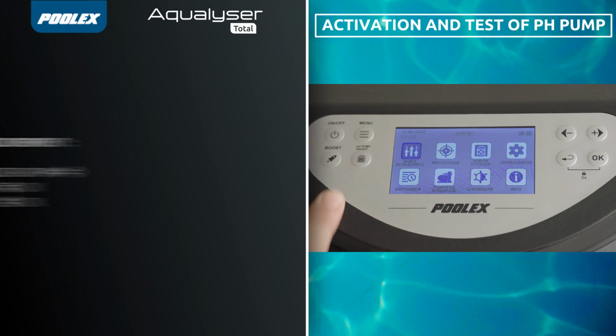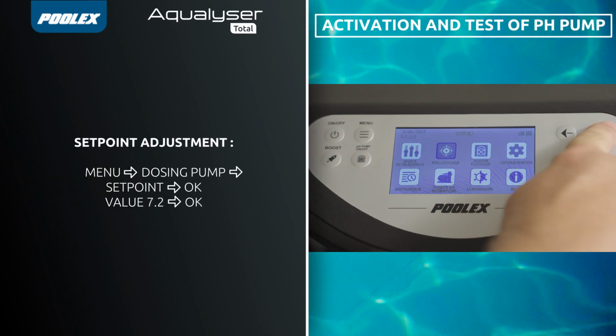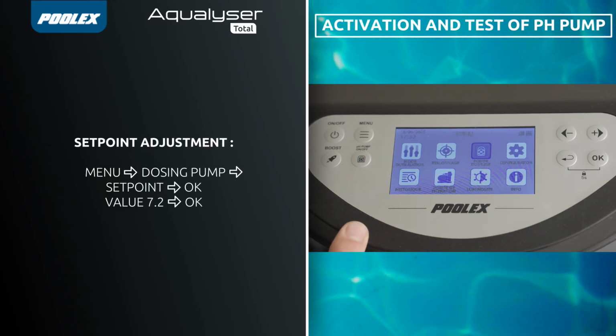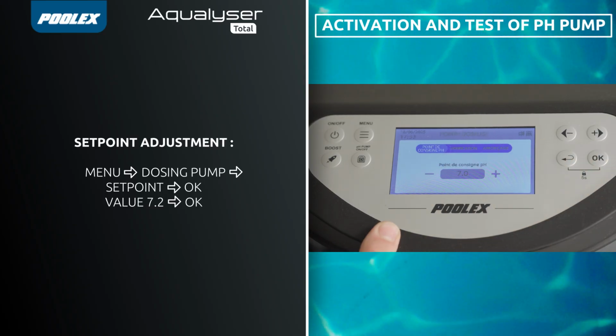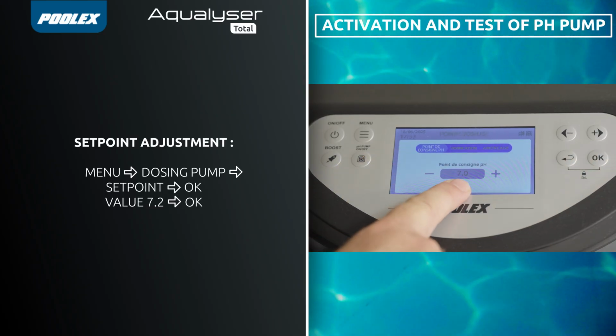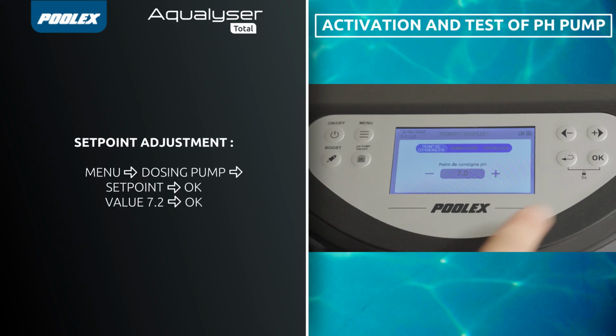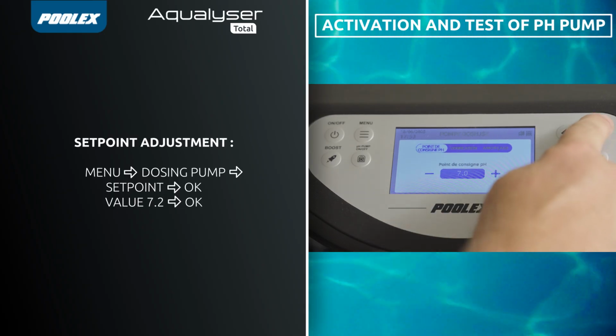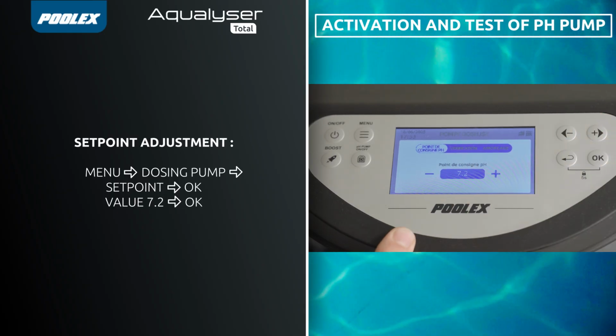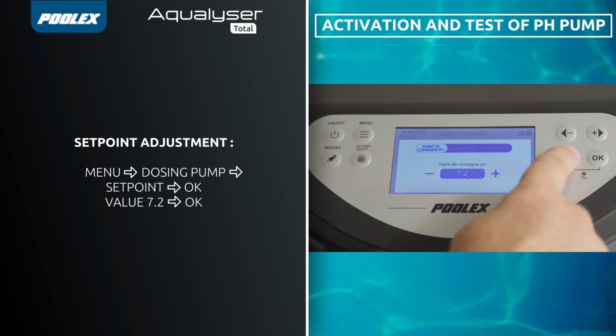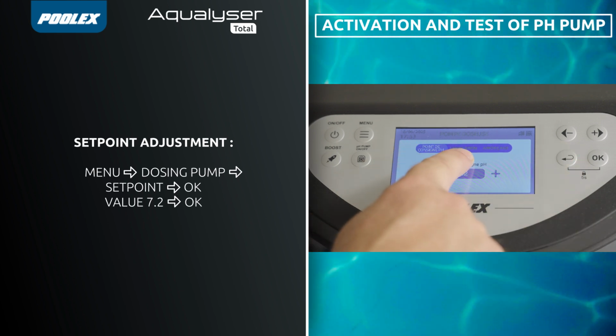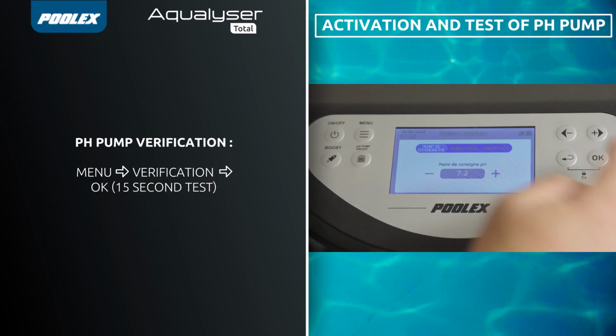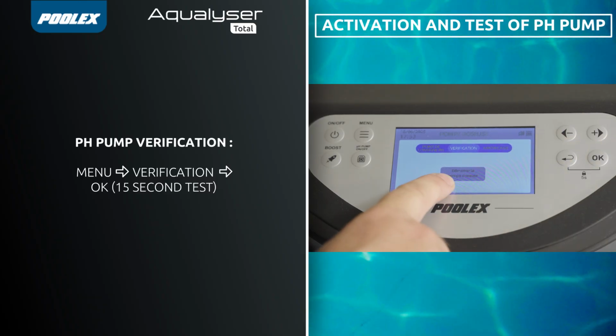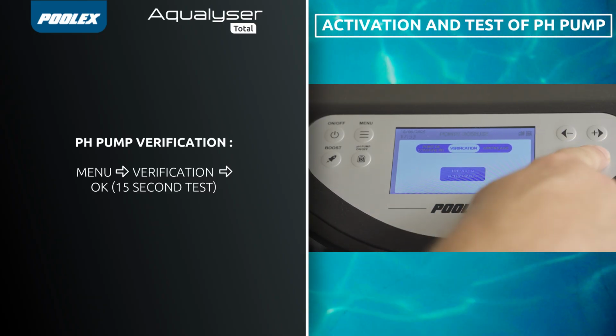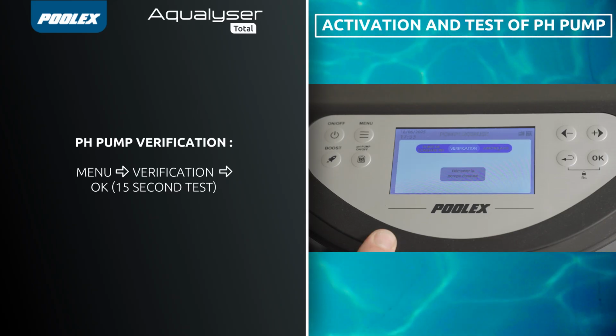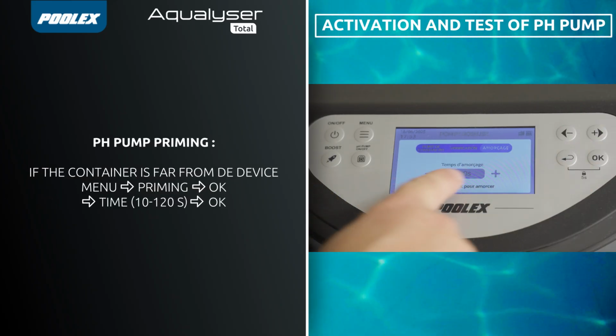In the menu, select Dosing Pump, then Set Point. The default set point is 7.2, adjusted with the plus or minus buttons. Then confirm with OK. To check the pump operation, use the arrows to go to Verification and start the 15-second test with OK. If necessary, prime the pump by selecting Priming.